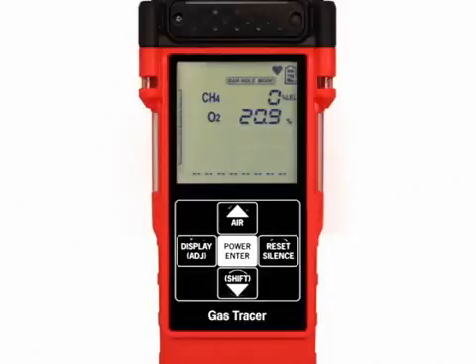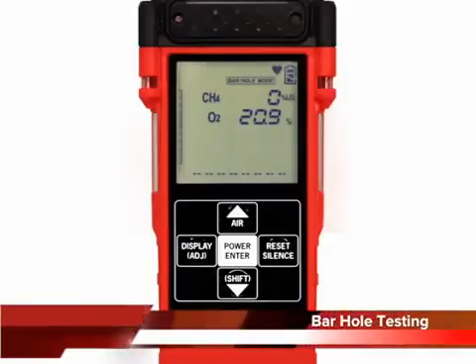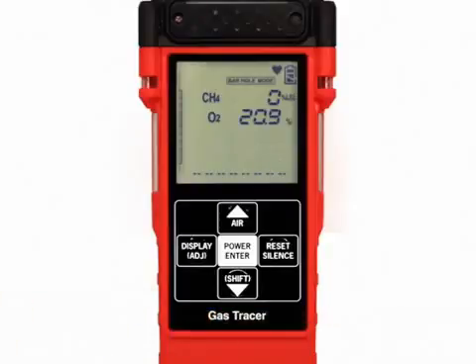The gas tracer is now operating in bar hole mode. The methane and oxygen channels are displayed along with the battery charge level. In bar hole mode, you can initiate sampling for a fixed time period to monitor for methane and oxygen in a bar hole. The factory set time is 30 seconds.